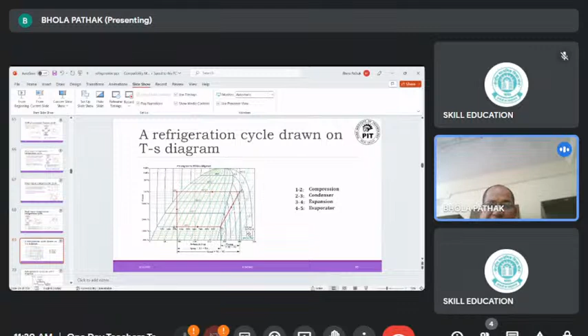So the work input will be H2 minus H1. Heat rejected is H2 minus H3, and heat absorbed will be H1 minus H4. So you can find the actual COP from this graph as H1 minus H4 divided by H2 minus H1. This will give you the COP of this cycle.